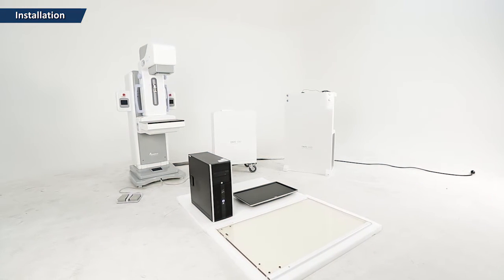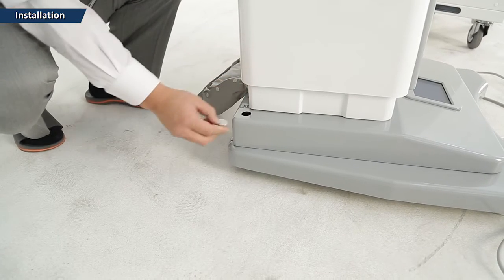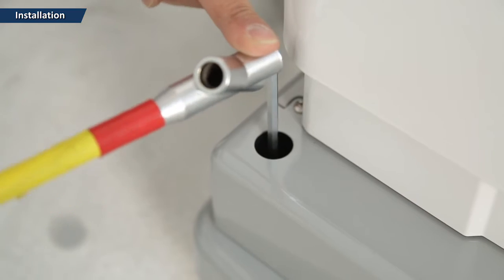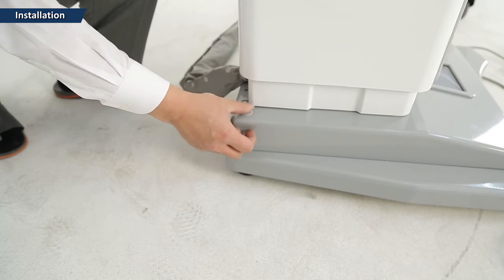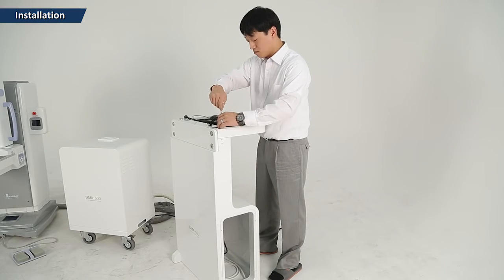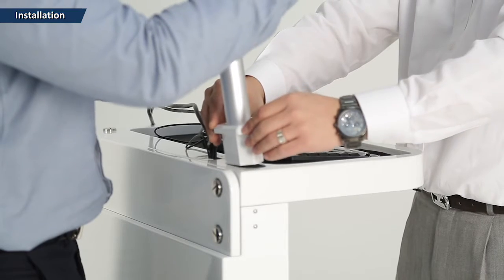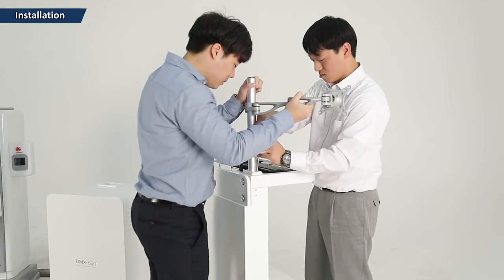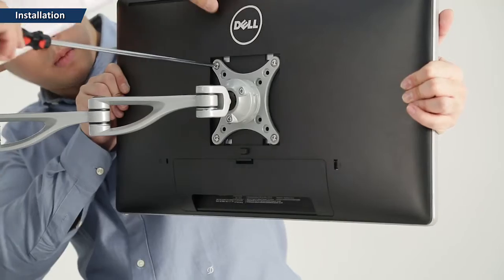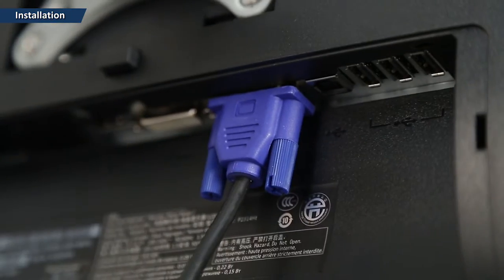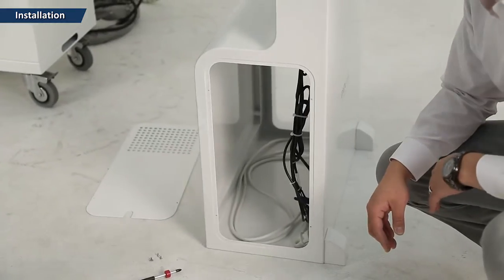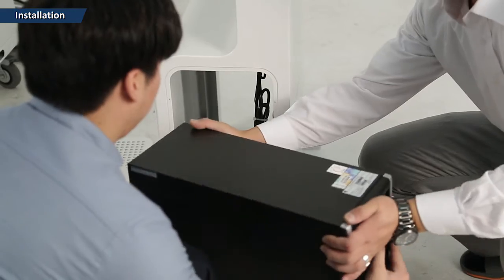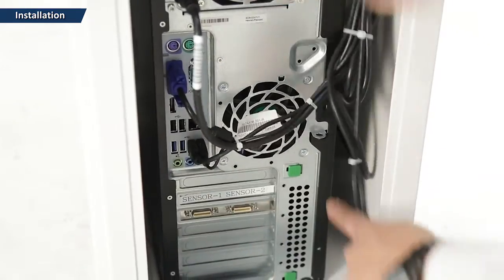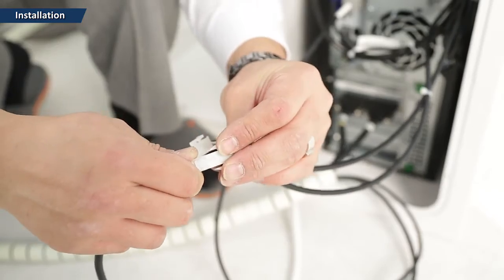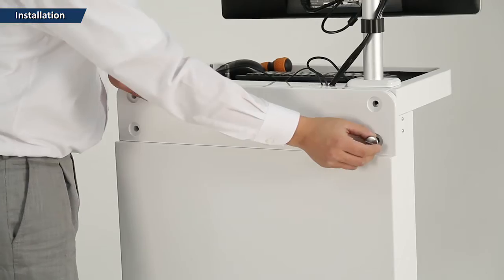Move to the place where you're going to install the machine. Once you have decided on the right spot, turn the leveler to level the machine and fix it. After installing the monitor, connect the cable. Place the PC desktop and connect the cables in order. Once the PC is connected, install the license key and cover the case.